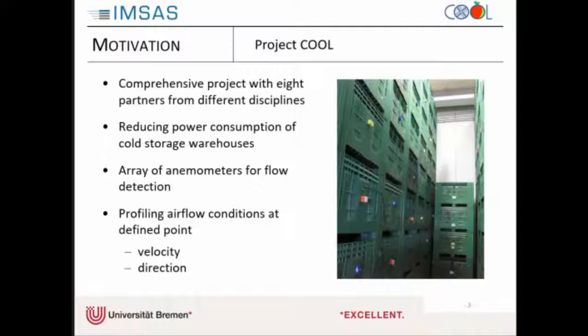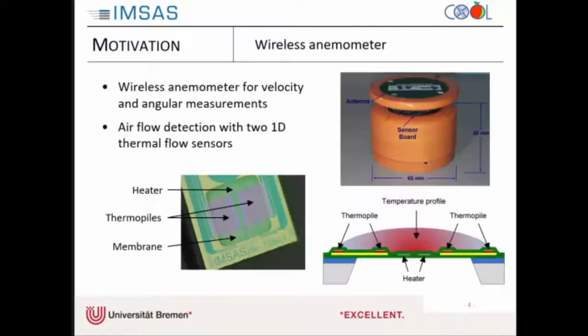For this, we built an array of wireless anemometers. You can see here the sides of the boxes, to detect the flow and make a flow map of the whole storage room. For this, we make the profiling for each point, with the profiling of the velocity and of the direction. So we build a wireless anemometer. It has a big body and a top plate, and between those there's a small gap. Through this gap, the flow can go through, and in the gap, there's a sensor board.